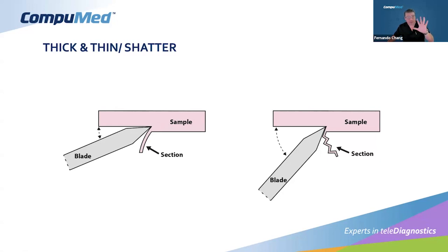And this is 5 microns, which, just to remind you, is a millimeter divided by 1,000. This is the thickness we are cutting. So moving parts cannot be allowed at this extremely tiny, minuscule, thin section thickness. If something is moving that is not supposed to move, like the blade is supposed to move, but the sample is supposed to be affixed, and perhaps the sample is not well fixed on top of the chuck, it's going to move, and it's going to give us a problem.